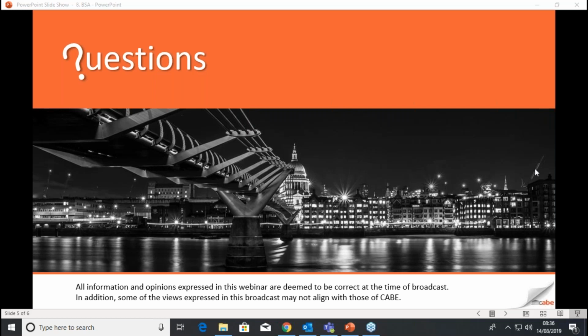Okay. So, now we have a question from Colleen, and she asks, how are sprinklers maintained and how often is advisable? Okay, so in terms of sprinkler maintenance, the head itself doesn't really need any maintenance. It really comes down to things like fire pumps and valves. Now, in industrial settings, fire pumps, if you've got a diesel engine, it needs running each week, and that can be run by somebody for half an hour. If it's an electric pump, it might need to be turned over for 15 minutes. Valves themselves, once a quarter, so every 3 months, you probably need to make sure the valves are manipulated.